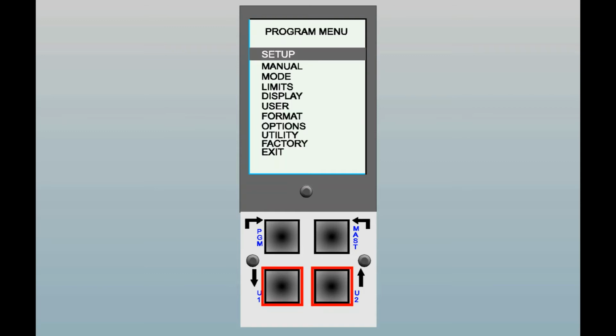The next item on the main menu is called Manual. This menu item allows for manual adjustment of the electronic zero and fine electronic gain. These two controls are changed automatically during the auto mastering process in order to calibrate the column on a periodic basis.